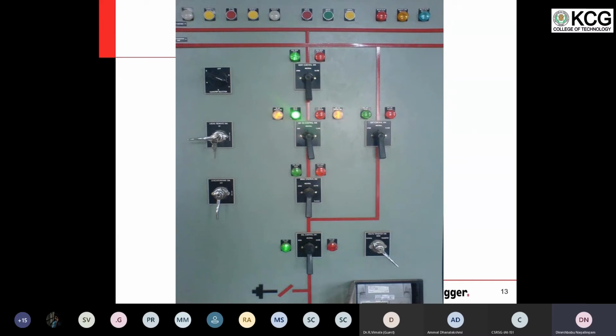What are the list of ANSI codes available? So there are total 95 numbers. That means you can say there are total 95 protection system. So the syllabus for power system protection is only 95, because globally ANSI code has given only 95 protection systems. So out of this 95, several protection functions are main protection and several are backup. For example, 89 stands for isolator, 52 stands for breaker. So these are not major protection functions. These are functions which are used to assist the protection function.